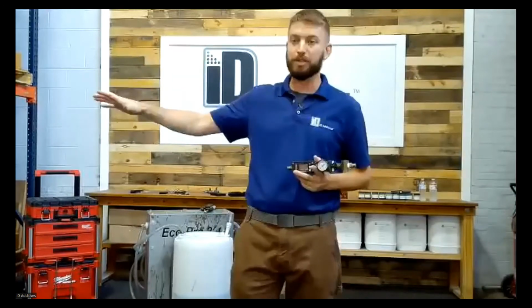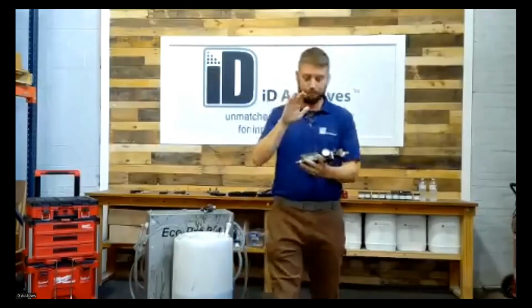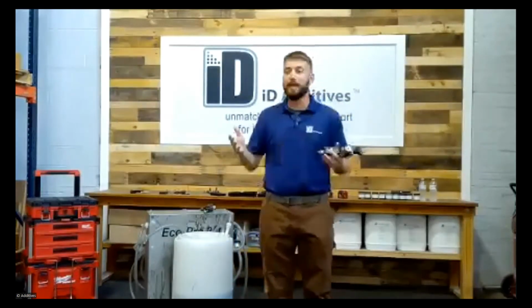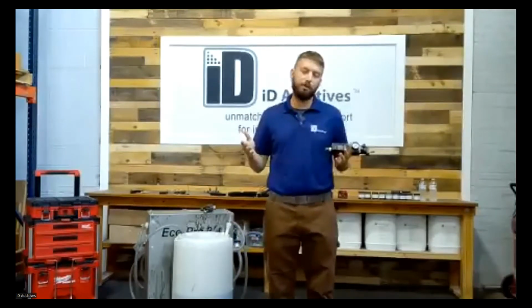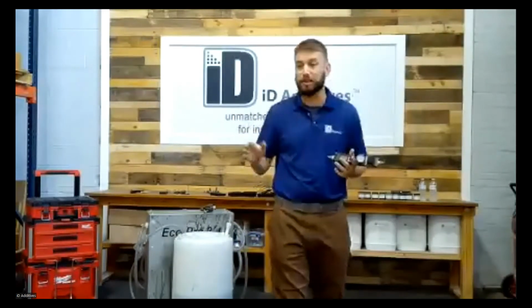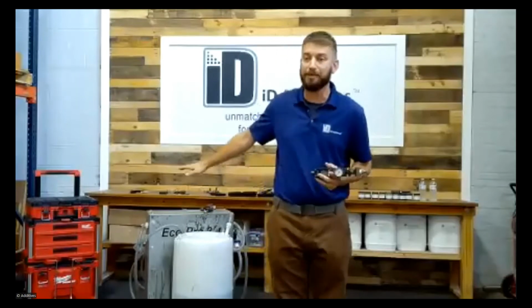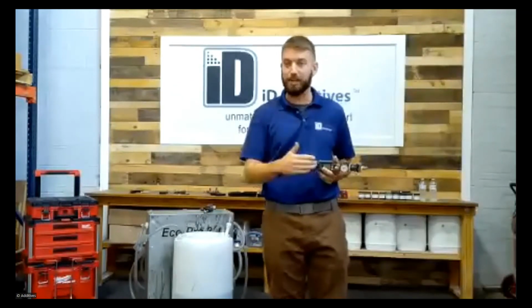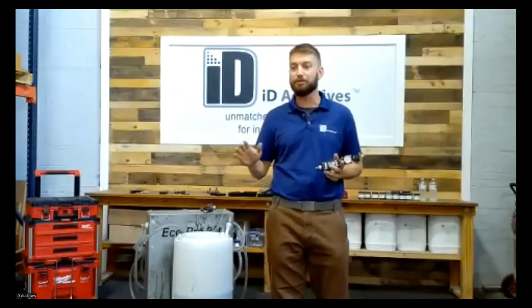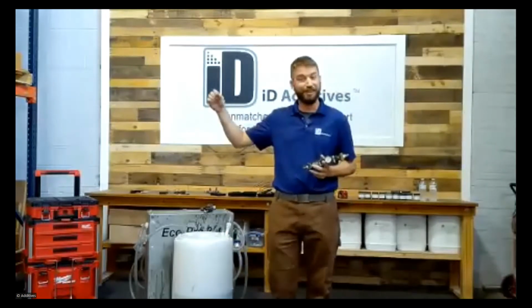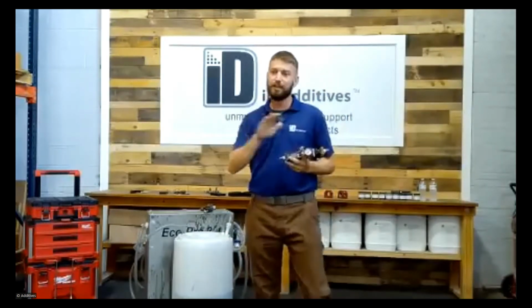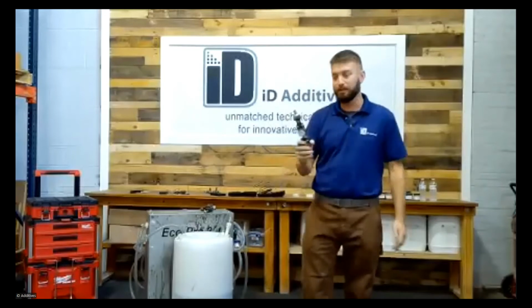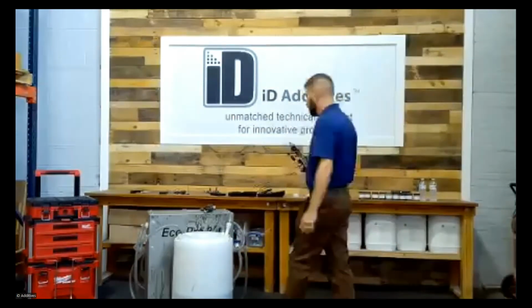Now you know your top benchmark is 5 GPMs for that tool. It runs production, lands back on your bench, and you hook up the flow meter. If it reads 4.9, that's within acceptable tolerance, so you don't even need to descale. If it drops to 3.5, you know you can get better flow, because you've seen it, benchmarked it, and documented it. We've got 5 GPMs, and we're all set to go.